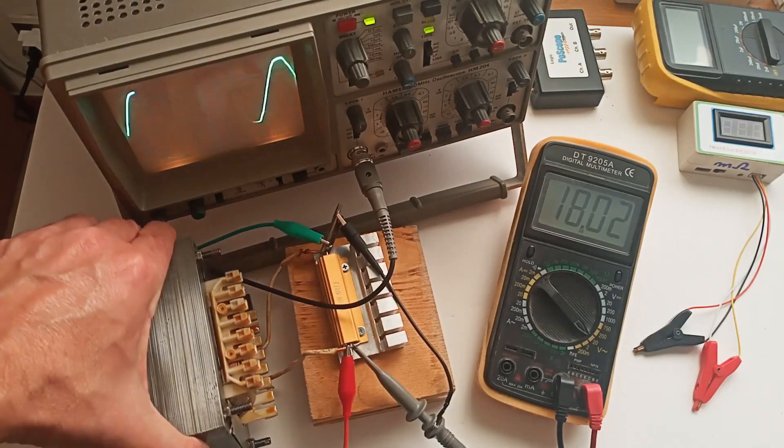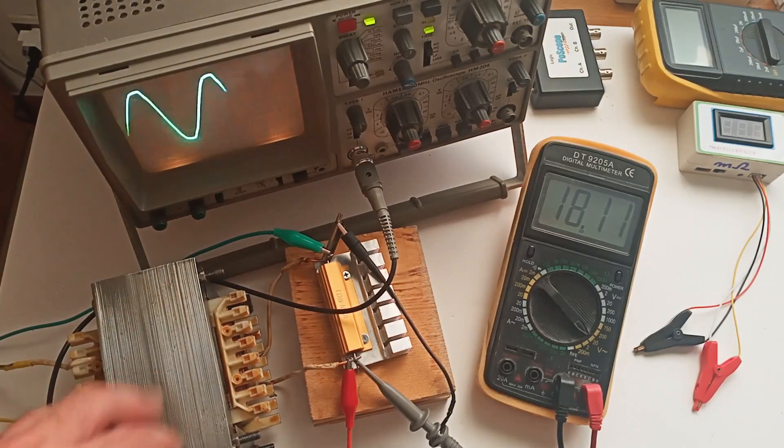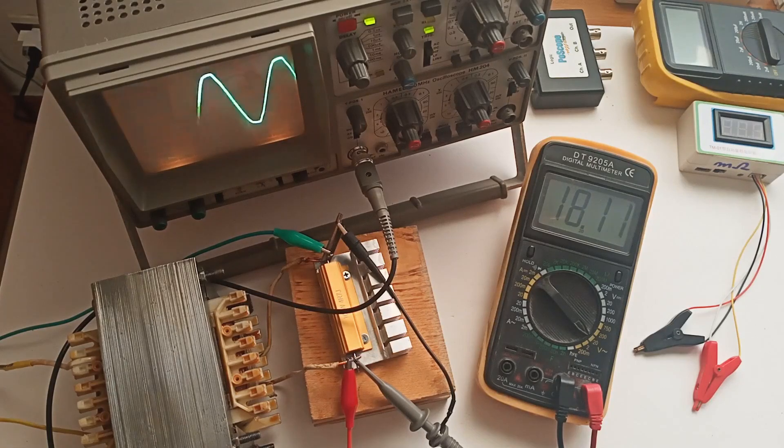To ensure proper operation of the transformer without excessive stress, the voltage drop with a connected load should not exceed 15% of the no-load voltage.